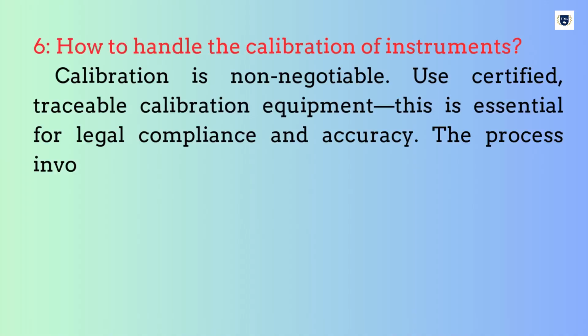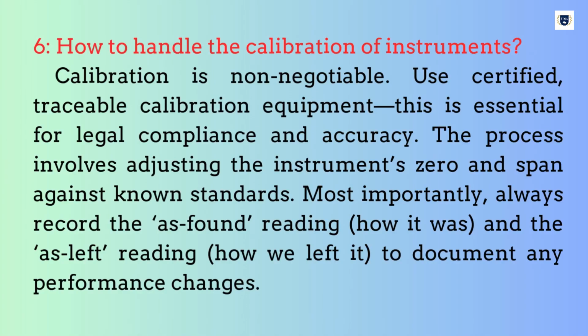How to handle the calibration of instruments? Calibration is non-negotiable. Use certified, traceable calibration equipment. This is essential for legal compliance and accuracy. The process involves adjusting the instrument's zero and span against known standards. Most importantly, always record the as found reading, how it was, and the as left reading, how we left it, to document any performance changes.